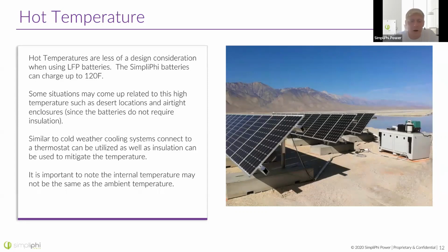Also, note that the battery's internal temperature is going to usually be less hot than the outside temperature unless you're charging. If you're charging the battery, it is generating a little bit of heat, might be warmer than the ambient, but in general, it's going to trail behind the ambient temperature slightly, just as it does in cold weather. So as the temperatures rise and fall, the batteries are slower to catch up, and they're always remaining more moderate than whatever the ambient temperature is.